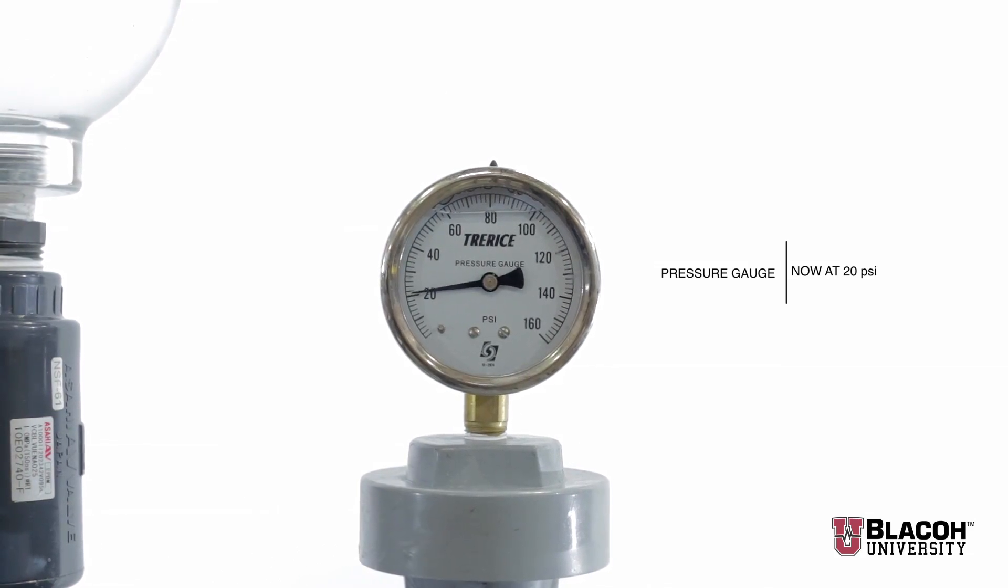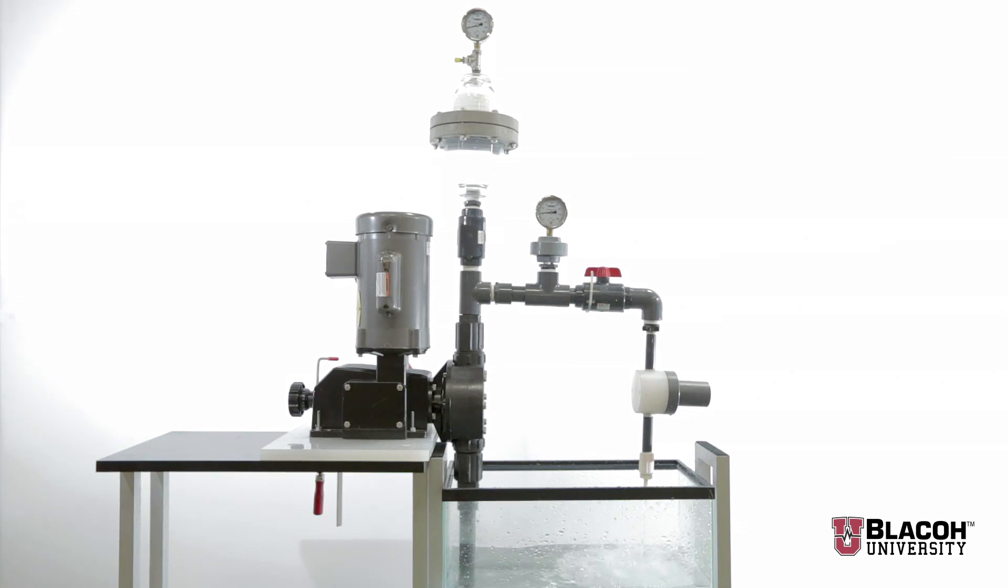With the benefit of pulsation dampener, the pump only has to overcome 20 psi to continue to discharge liquid, not the 50 psi created without the dampener.